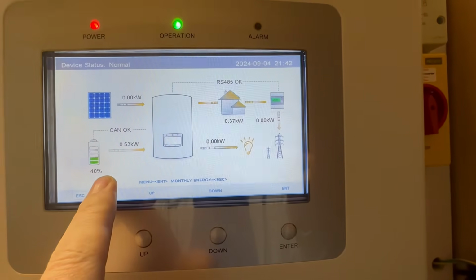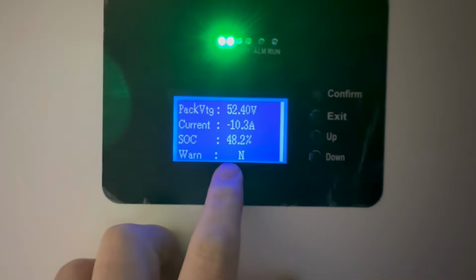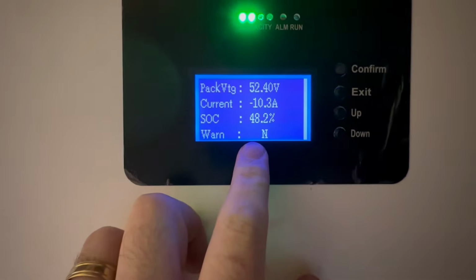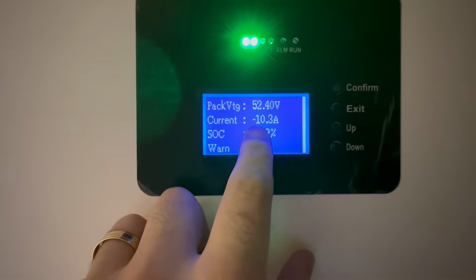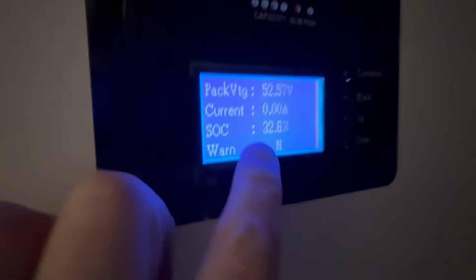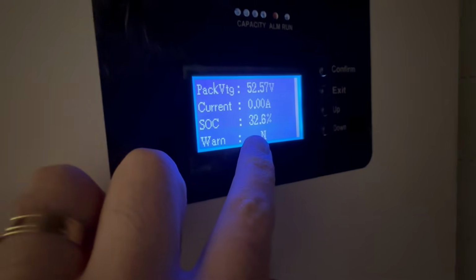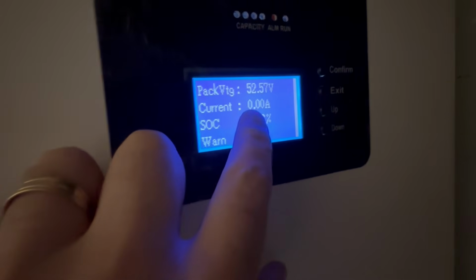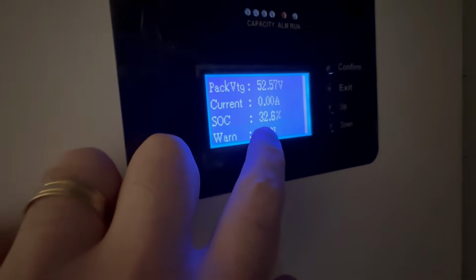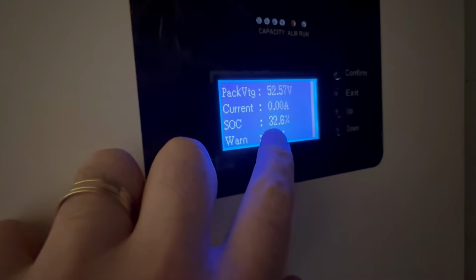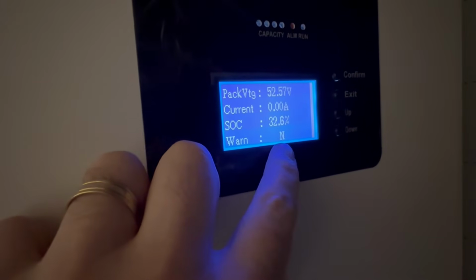Noting here that we have 40%. If we move to the first battery, our state of charge is 48%, and it's drawing around 10 amps from that battery. If we move to the second battery, we're at just over 32%, and nothing is being drawn from there. So between the 50 odd and the 30, you're averaging out at 40%.